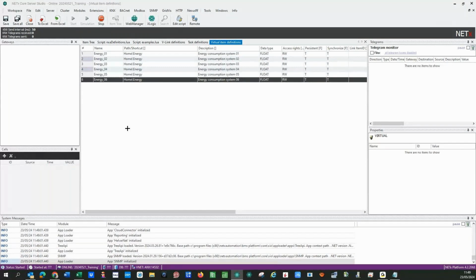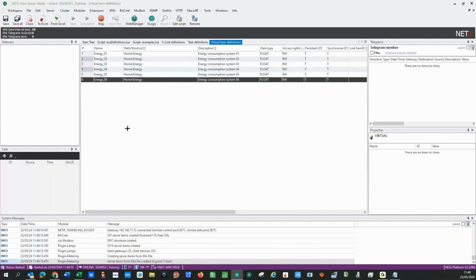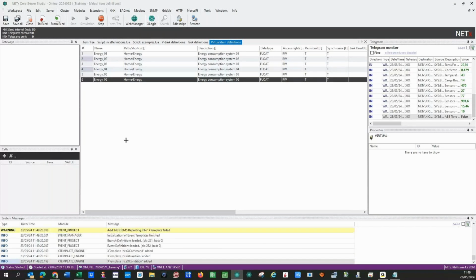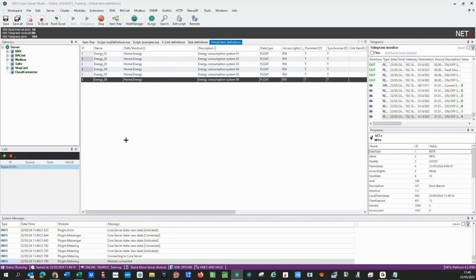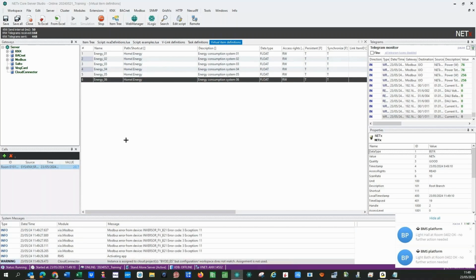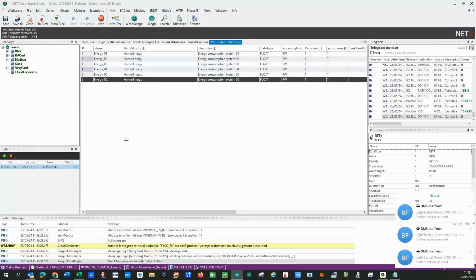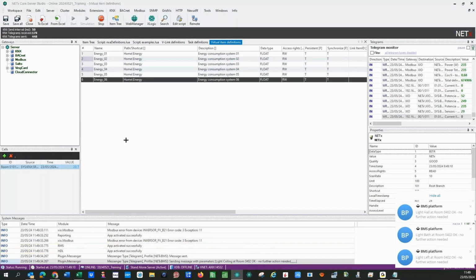If you want to add values, those values cannot be Boolean, because true plus true is not 2, it's true. It's like a funny sentence, but true plus false is not 1, it's just true. It's not possible to add Boolean values. So we need to convert these values into numerical values. So we can use scripting to do this. And then, as a second approach of this script, maybe we can even give values. When it's on, it can be 20, and when it's off, it's 0.